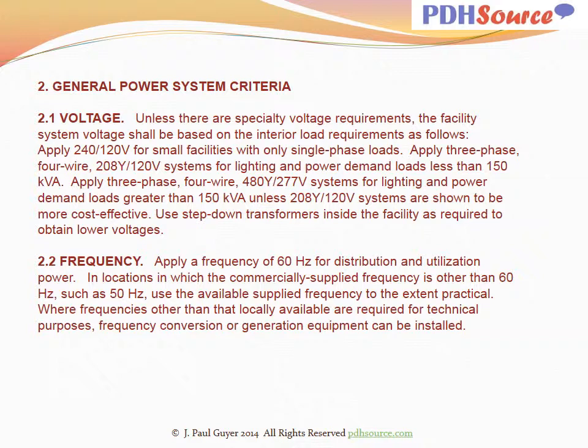Apply a frequency of 60 Hz for distribution and utilization power. In locations in which the commercially supplied frequency is other than 60 Hz, such as 50 Hz, use the available supplied frequency to the extent practical. Where frequencies other than that locally available are required for technical purposes, frequency conversion or generation equipment can be installed.